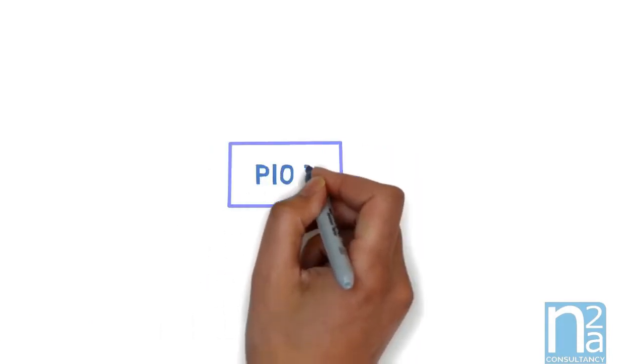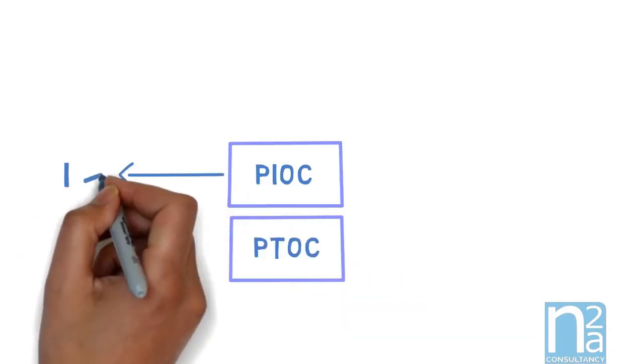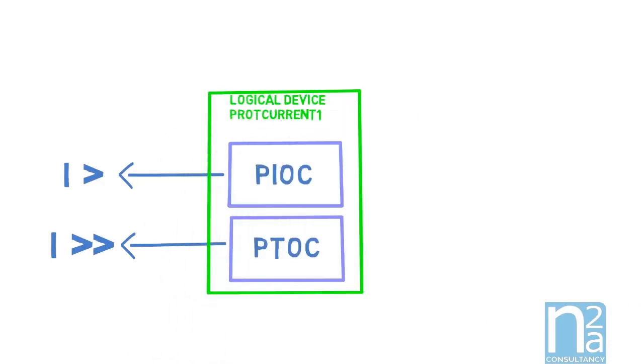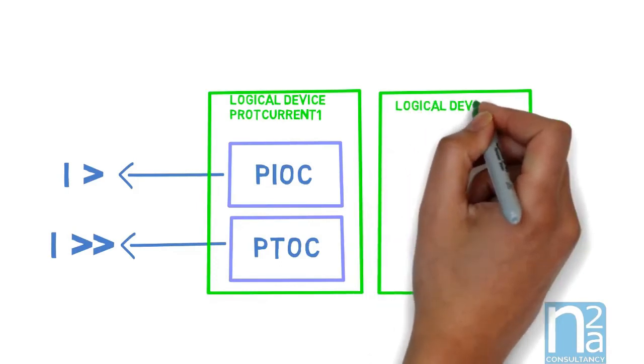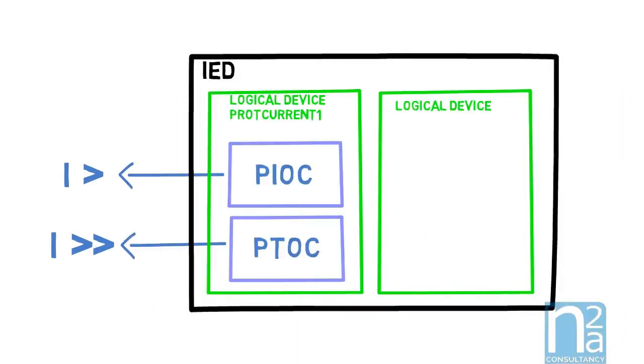IEC 61850 gives the possibility to group logical nodes into a logical device, but this choice is free. In this example, we have grouped instantaneous over-current and time over-current into a logical device we called prot-current 1. Last, we have the IED which groups the various logical devices implemented. This detailed definition must be followed to allow multi-vendor compatibility.